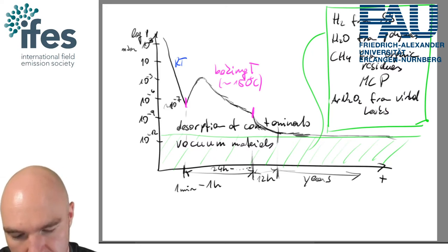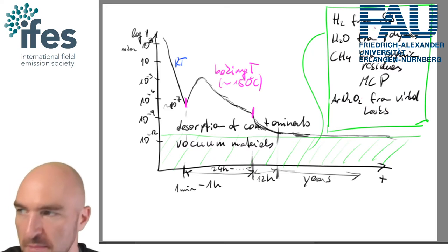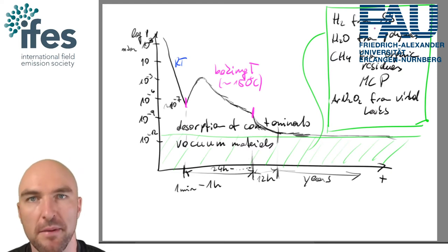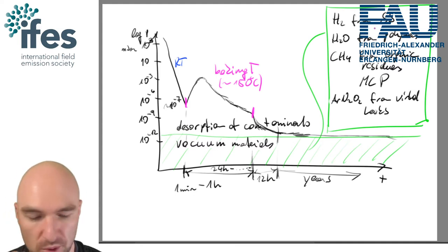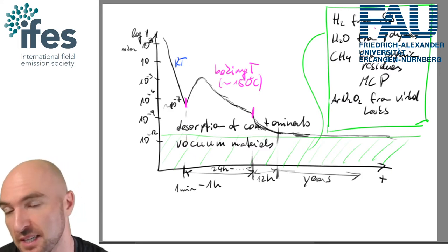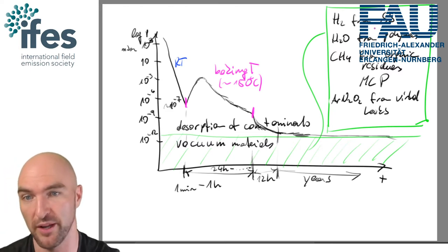Let's put it here as well, so we can have argon, nitrogen, oxygen from virtual leaks. So again, this list is not fully exhaustive because if you, for example, have aluminium parts, then you have an aluminium hydroxide where you can get things coming out of the hydroxide.